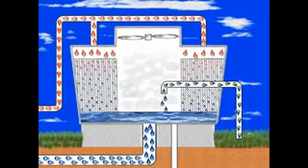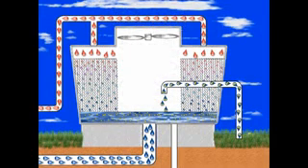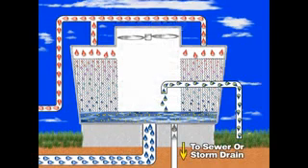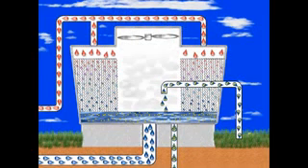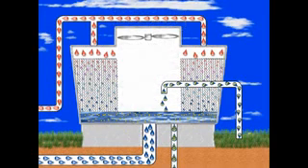This fresh makeup water carries additional elements into the system water where they accumulate. The more water that evaporates, the greater the need for makeup water to replenish the system, and the faster the concentration of elements builds. To reduce the concentration of elements in the system, a bleed-off valve opens and dumps a portion of the system water to drain as wastewater. This wastewater discharge must also be replenished by adding more fresh makeup water. Because makeup water carries fewer elements than the system water, it will slowly reduce system concentration. During normal operation, evaporation, bleed-off, and makeup are balanced to maintain the proper water volume while creating a continuous open loop.